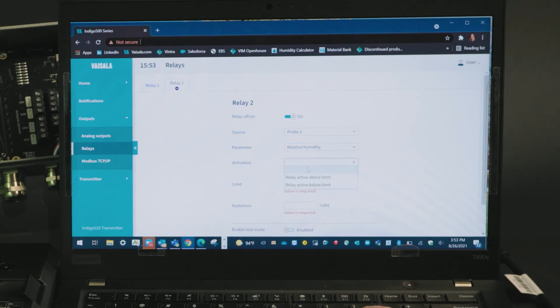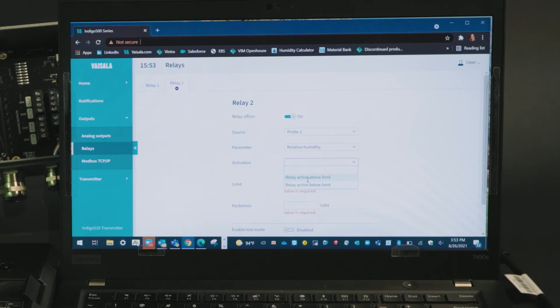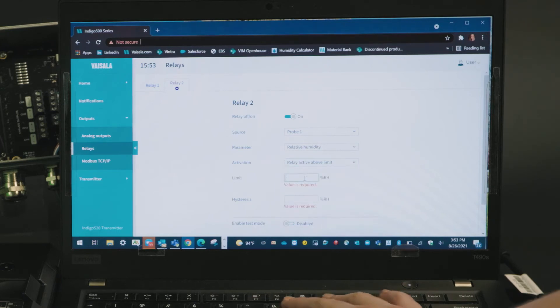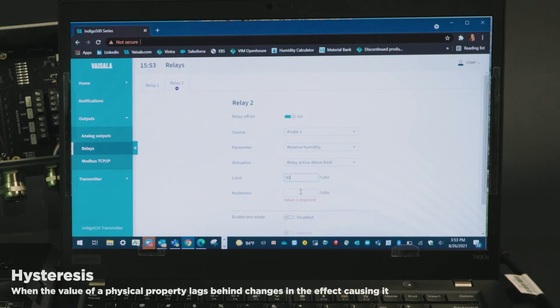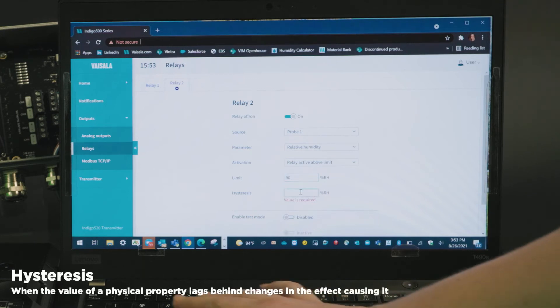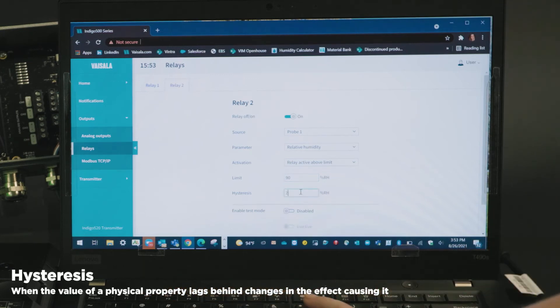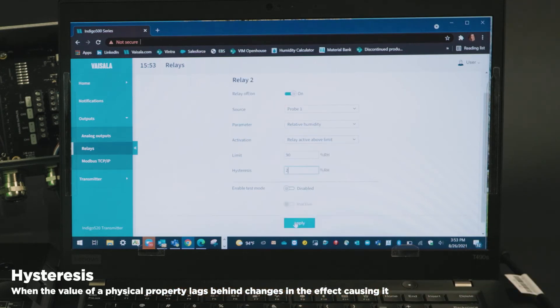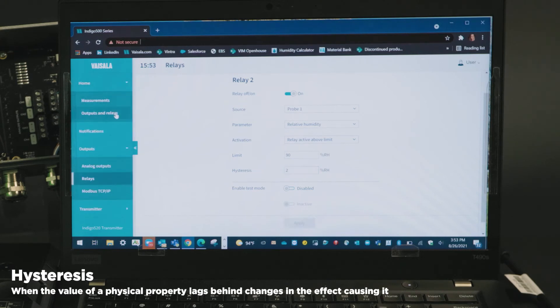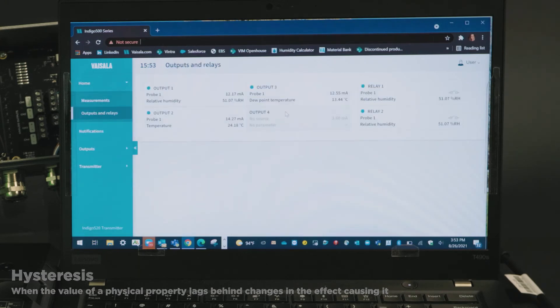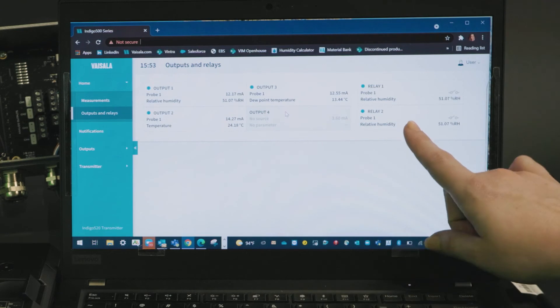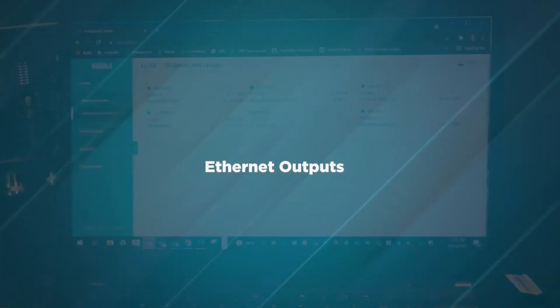Activation when above limit, because I want an alarm once I hit 90 or above limit value. And then hysteresis I'll say two percent. Go ahead and hit apply and if I navigate back home into outputs and relays I can confirm the second relay is set up.